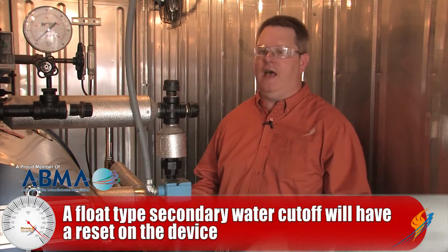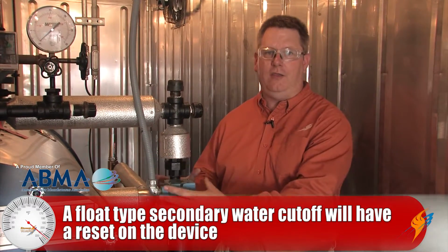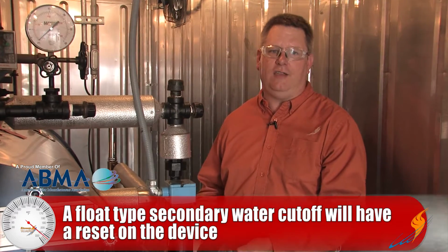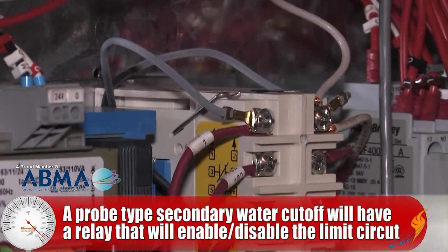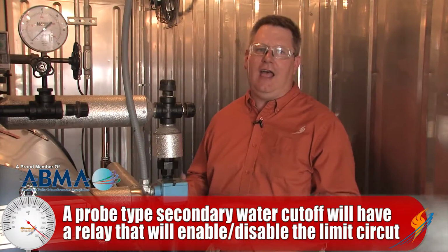One difference between a probe type secondary low water cutoff and a float type is that a float type secondary will have a manual reset button in the immediate vicinity of the device. On a probe type low water cutoff, we have a relay that's enabling or disabling the limit circuit, and so that reset button may be remotely located. In this case, it's over on this panel.